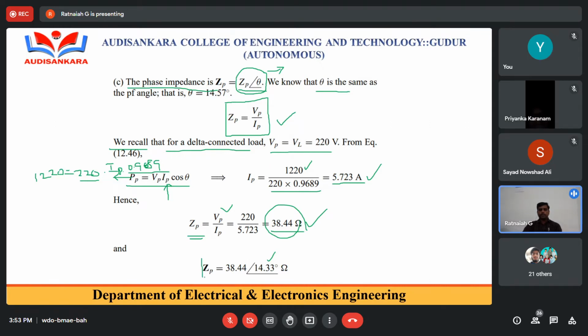So finally, the per phase impedance of the three-phase system is 38.44 at an angle of 14.33 degrees ohms. So this is the way to calculate per phase impedance, phase current or line currents, and all other components for the given problem.